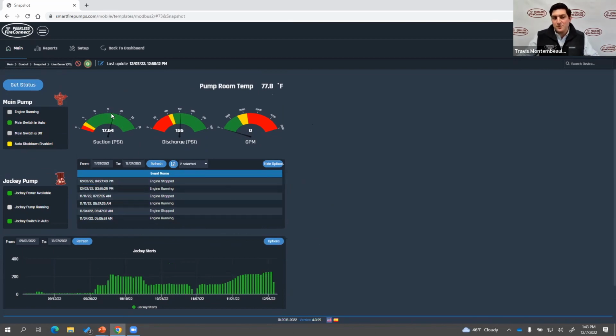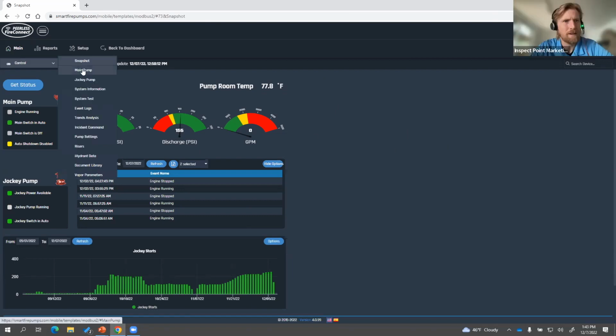And I think an important piece, Drew, to mention, we talk about APIs and sending data out. We can send any of this out, obviously with the approval of the end user, what they want to see, what they're willing to send out. But this can go to an inspection platform if you need it to. So if you're running down your weekly test and you have to mark off suction pressure and pump room temp, for example, that's already done for you effectively. Any thoughts about turning on a camera when it starts?